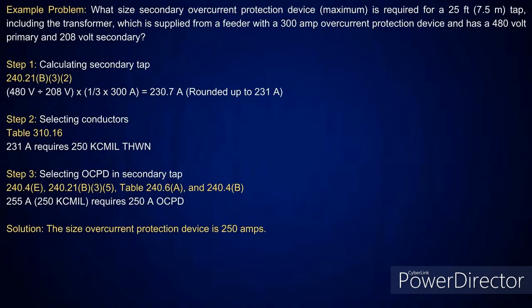All right. So we already know what the protection is upstream. So all I need to do is the secondary. Well, I said, if you have a transformer in there, we have to get the ratio of the transformer, right? So you're going to take the 480 volts, divide it by the 208 volts, and then you'll multiply. Basically, you got 300 amps multiplied by a third, which is 100 amps. So you'll take the 100 amps times that multiplier, which is going to give you 230.7 amps, just rounded up to 231 amps. Now this is where it gets interesting, because if you've got the 75 degree C terminals, you go look at table 310.16. It's just barely over 230 amps, which is a 4-aught conductor. But sticking by code, the next size actually above that is 255 amps, which is a 250 kcmil conductor.